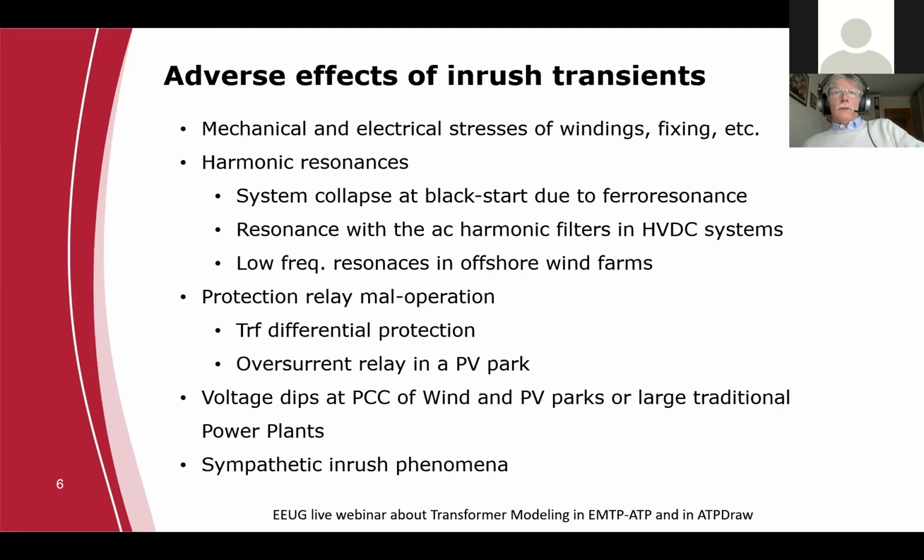If we have a nonlinear transformer and the relationship between the voltage and current becomes nonlinear, it might have some consequences for the operation of our protection relay system. We know very well that in the case of transformer differential protection, the biggest problem is how to solve the issues caused by the inrush current of the transformer. A similar issue may appear even for overcurrent relays. Sorry, I see some typo here, I will correct it.